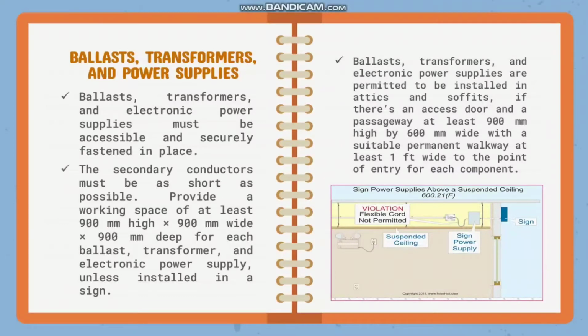So, dito sa picture is makikita na ang violation is yung power supplies per sign or yung equipment is connected by a flexible cord. So, violation yun. Kasi, ballast transformers and electronic power supply for signs can be located above a suspended ceiling, but the equipment can't be connected by a flexible cord. So, because yung flexible cord is not allowed to be installed through or above a suspended ceiling, as per chapter 4. So, nandun yung provision for the flexible cord or requirements for the flexible cord.